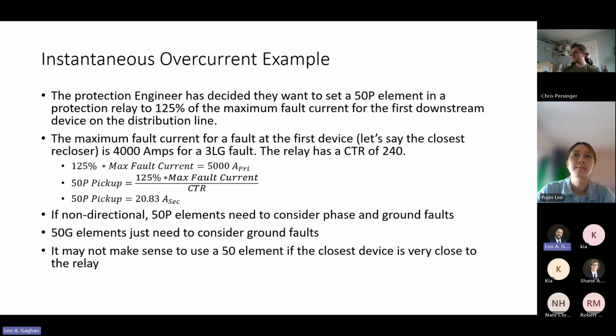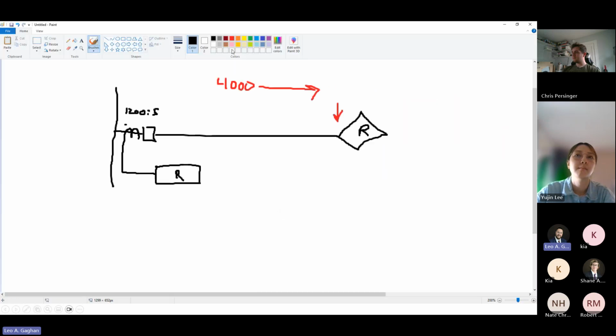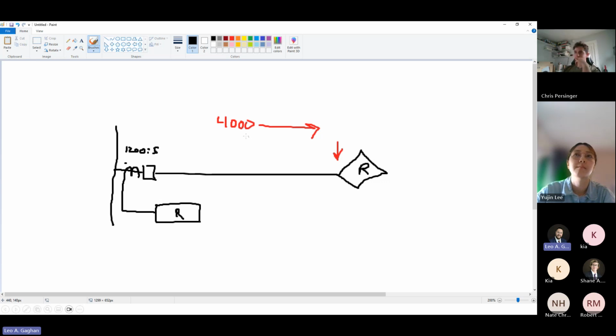And then lastly, it might not make sense to use a 50 element if the closest device is very close to the relay. And by that I mean, let's say this was a case where we're going to get 4,000 amps for a fault right there, but for a fault right here, we're only going to get 4,010 amps. Maybe just because this is a 200-foot line. Electrically, there's really no difference between this spot and that spot. It's next to impossible to distinguish faults in those two different locations. You may say that and decide it's not worth it. So again, different companies will usually have different standards on how you make that decision. But it's a consideration.